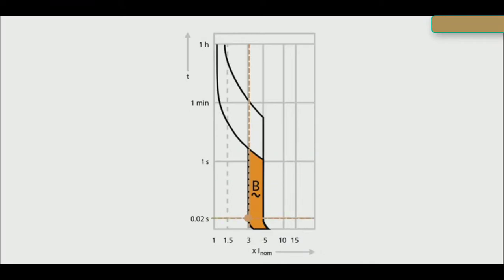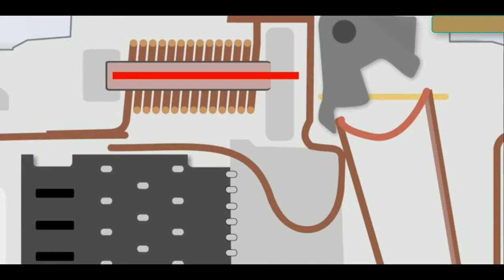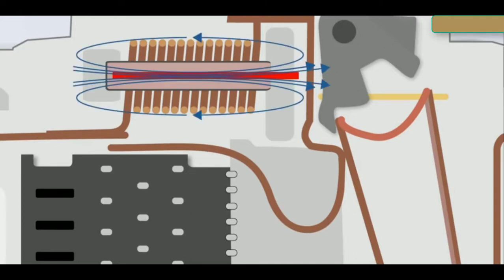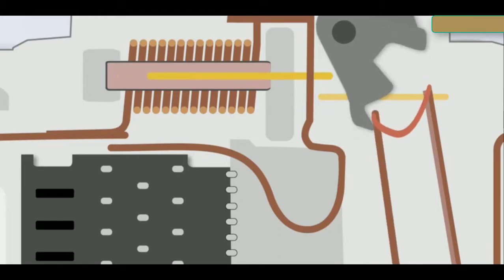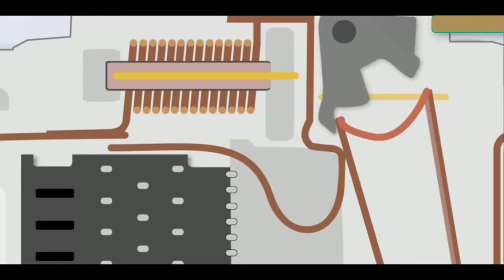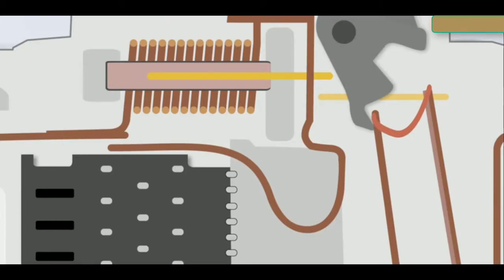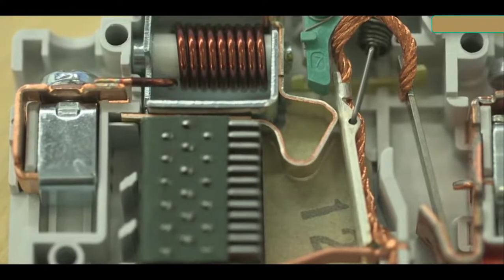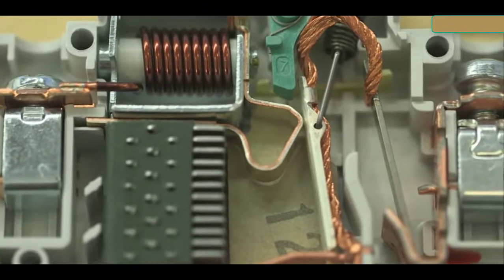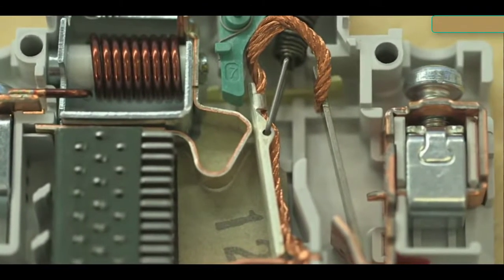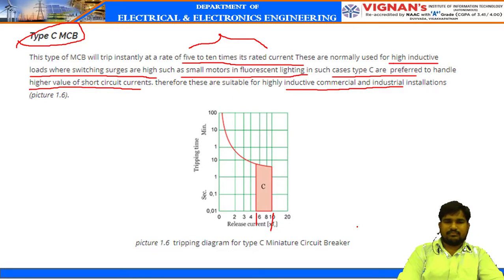An MCB must open a circuit instantaneously when it encounters a short circuit at several times the nominal current. A solenoid and a piston are the elements used for instantaneous tripping. A short circuit creates an instant magnetic field that moves the piston and operates the breaker. Interrupting high fault currents can result in heavy arcing. Due to magnetic forces, the arc moves through a stack of metal plates where it is cooled, split, and finally extinguished at the next zero crossing. Despite its small size, an MCB has a rather sophisticated design consisting of two separate tripping mechanisms for overloads and short circuits. Observe the ratings of MCB.